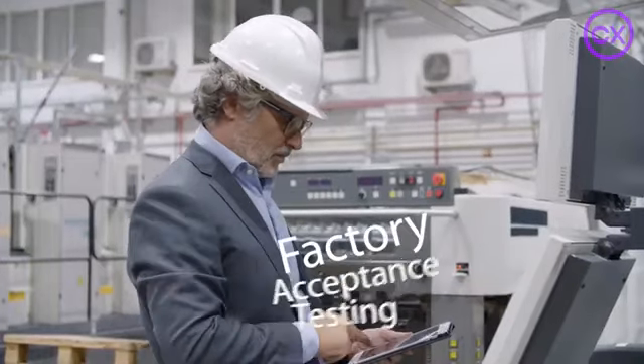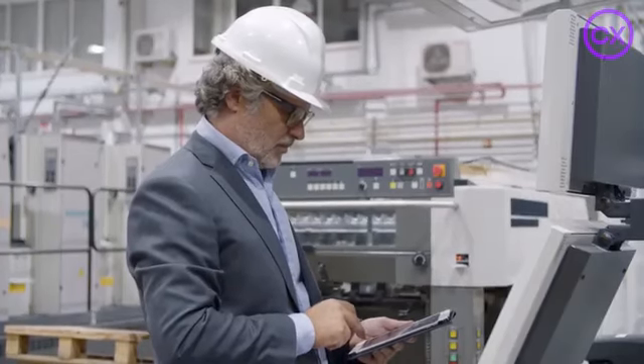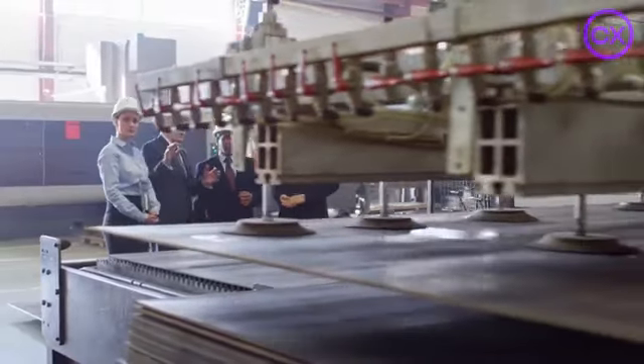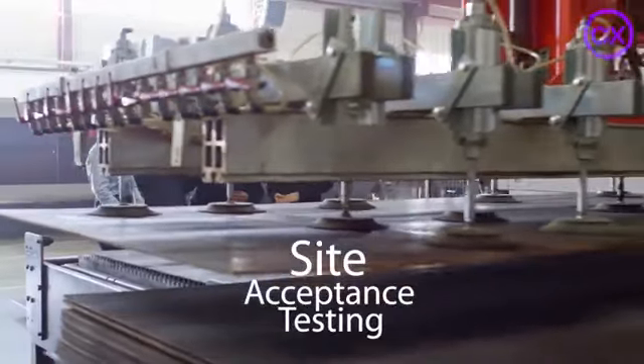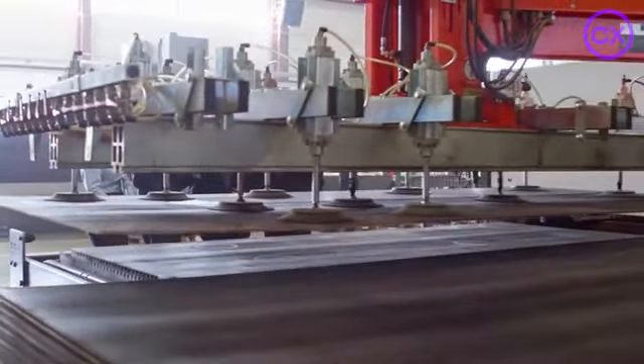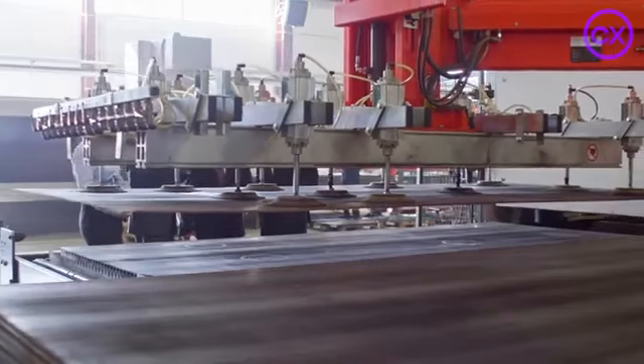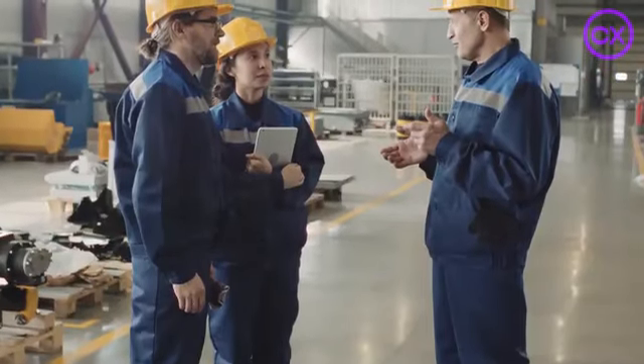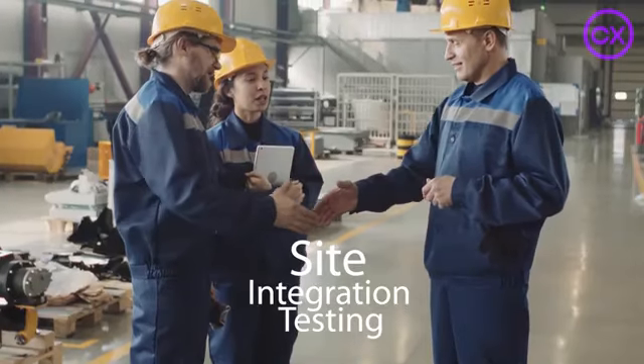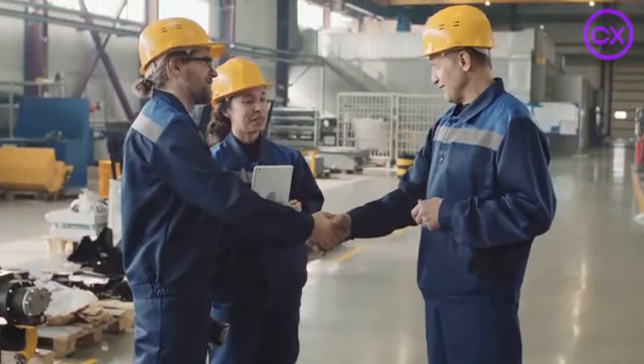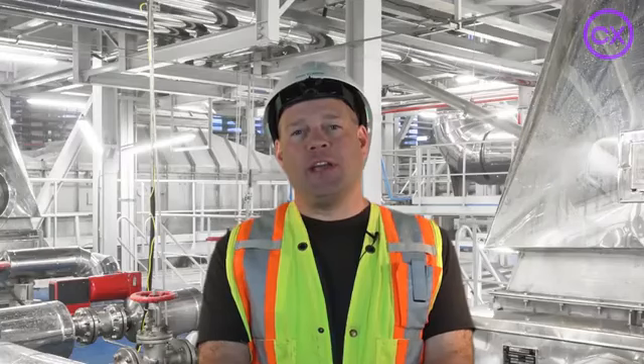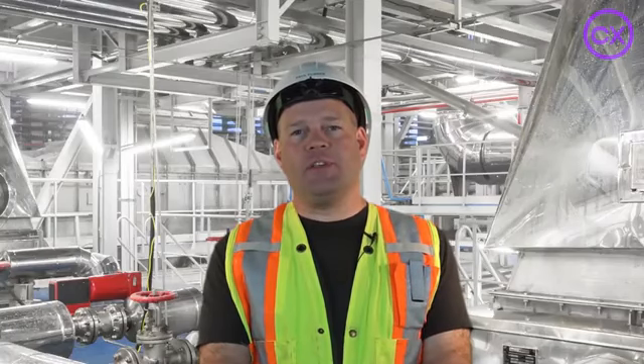FAT, or factory acceptance testing, is the testing that's conducted by the manufacturer in the factory prior to shipping to site. SAT, which is site acceptance testing, is the testing that's conducted in the field, either by the vendor or by the on-site commissioning team. These are the standalone tests to confirm no damage during shipping or installation. SIT, or site integration testing, is the testing conducted in the field to confirm equipment functions as a system. Pre-commissioning activities vary depending on the equipment to be tested, for example, mechanical versus electrical subsystems.